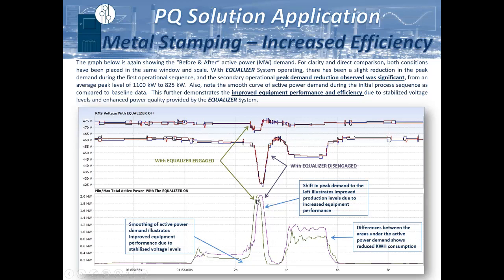Much like what we saw in the video on startup conditions, the equalizer system can actually replace the need for soft starts on a network. Because if the only purpose of that soft start is to minimize the voltage drop or its duration, and it's not required by the process, then the equalizer is the one providing that voltage stability. So the soft start may not be required. In that one video, towards the end, it showed where a single equalizer system was designed and utilized as the soft start for medium voltage water pumps. So instead of having to purchase 4 medium voltage soft starts or 4 medium voltage VFDs, now they can just have one equalizer system that performs that functionality.